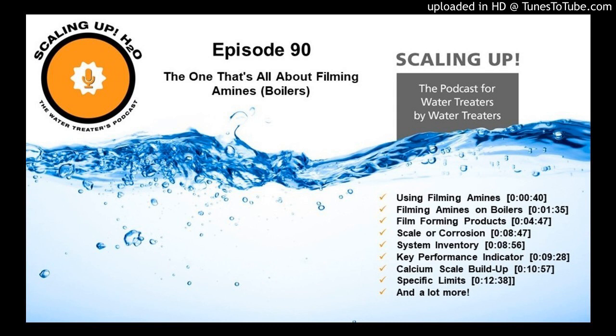Absolutely. Marodi, are there any systems or any conditions that you know of that you would say, you know what, you don't want to use this product for that? Ooh, if your corrosion is truly kind of holding the system together, this is probably not a good fit, because the filming amines really don't care. They will just continue to scrub whatever loose debris they can until they get to a surface that they want to stay attached to. And we could end up with a problem.